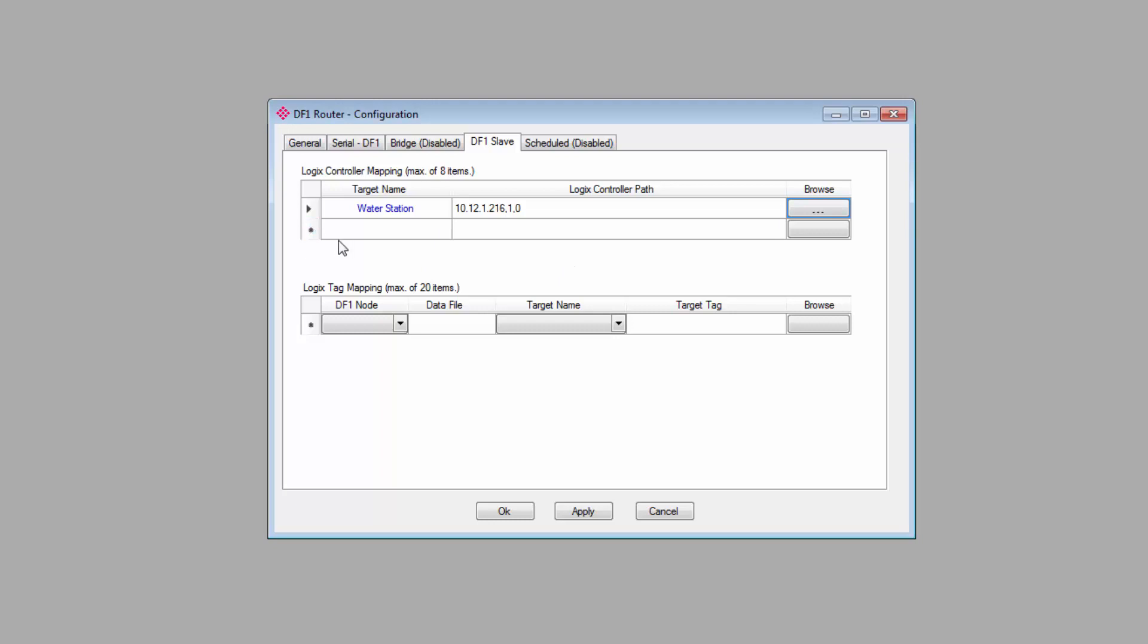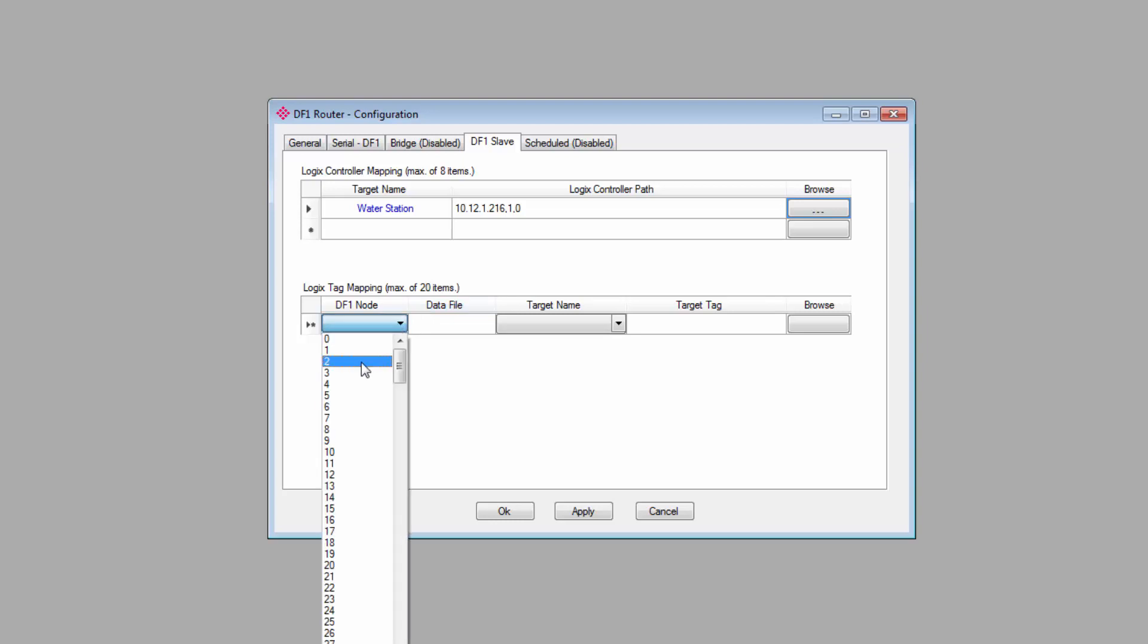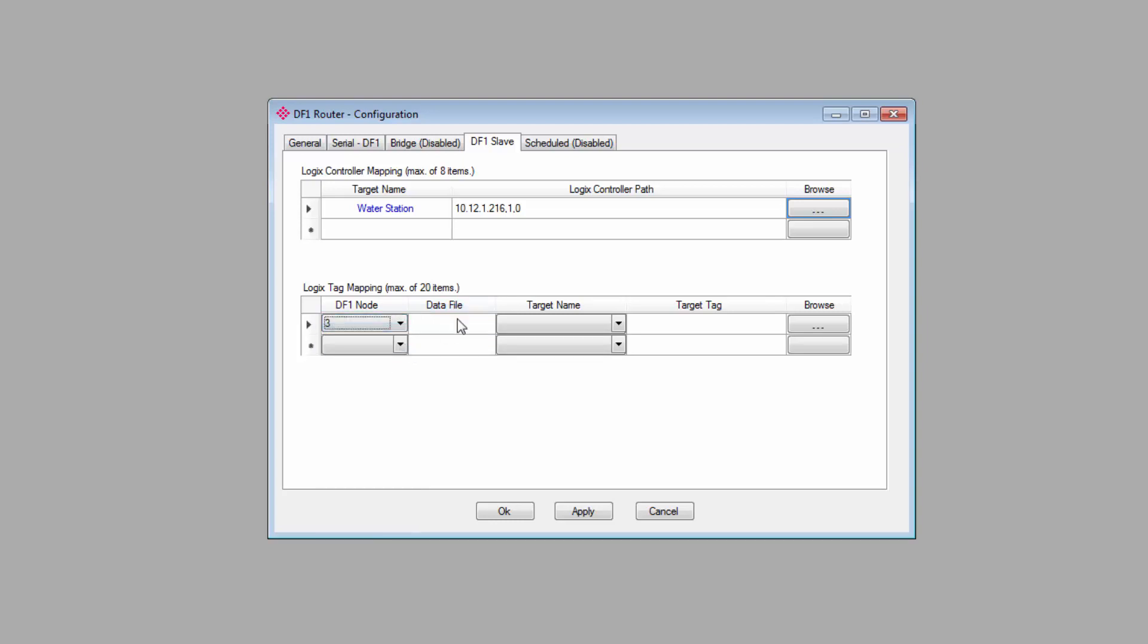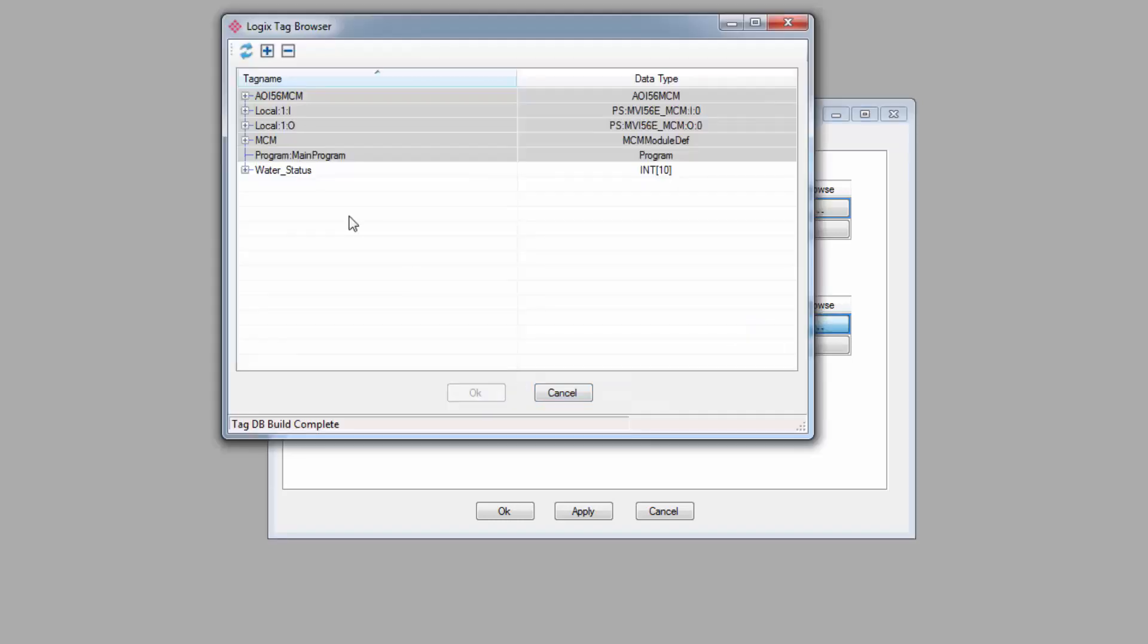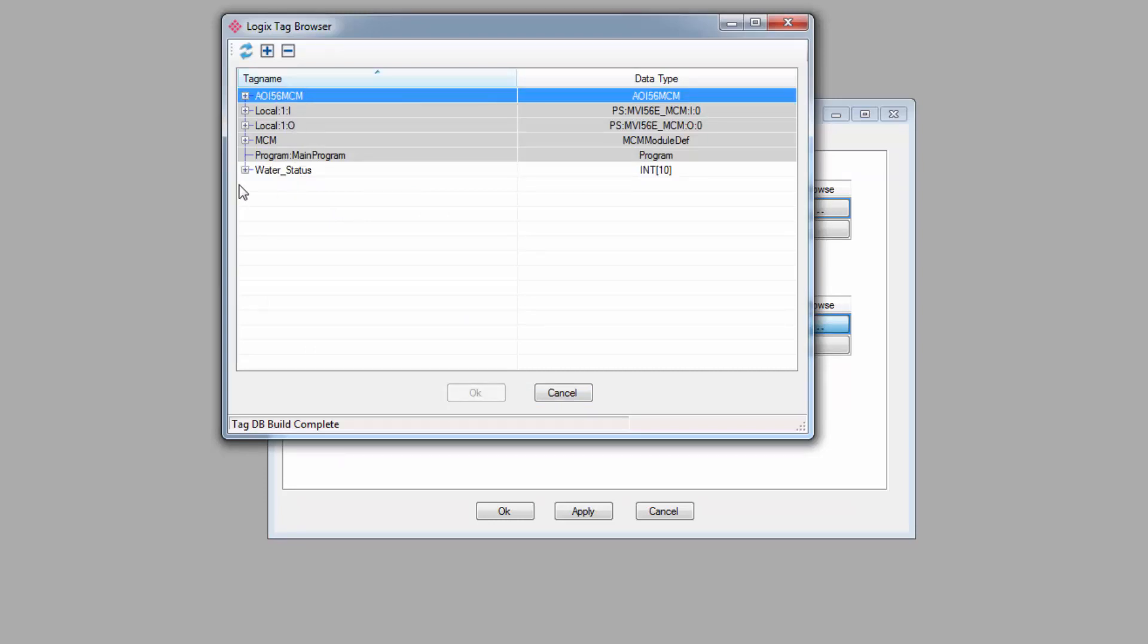At the bottom, under Logix Tag Mapping, you'll specify the node or nodes the PLX51 should emulate, and the corresponding data files will be mapped to the controller tags. First, enter the DF1 node that the PLX51 will emulate on the network. I've selected node 3. Next, enter the data file that node is expecting to read or write to. For me, it'll be N7. The target name corresponds to the Logix controllers identified above. So for me, it's Water Station. And then, the target tag is the target controller tag in the Logix controller. Simply click the Browse button, and you can browse your Logix controller.